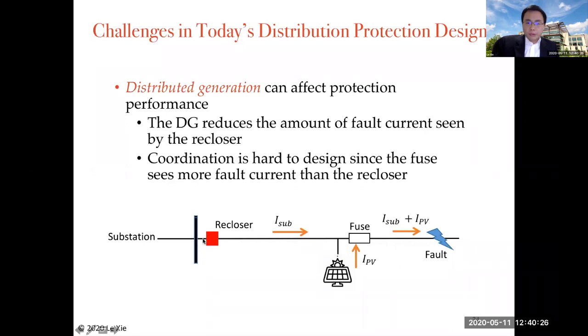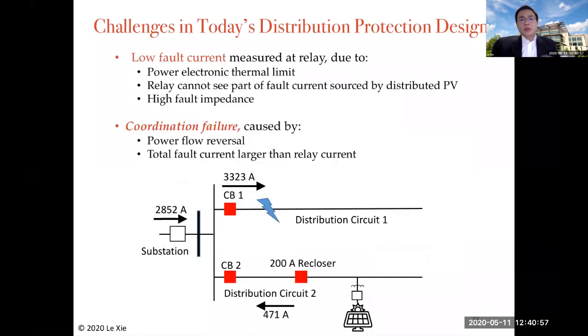So the red colored recloser becomes confused, because what it sees is this I-sub, and this I-sub is not substantially higher than a normal situation. So it gets confused: is it a faulty situation, or just a little bit of an increase in current, which happens all the time? So one needs to be better at tuning those points.